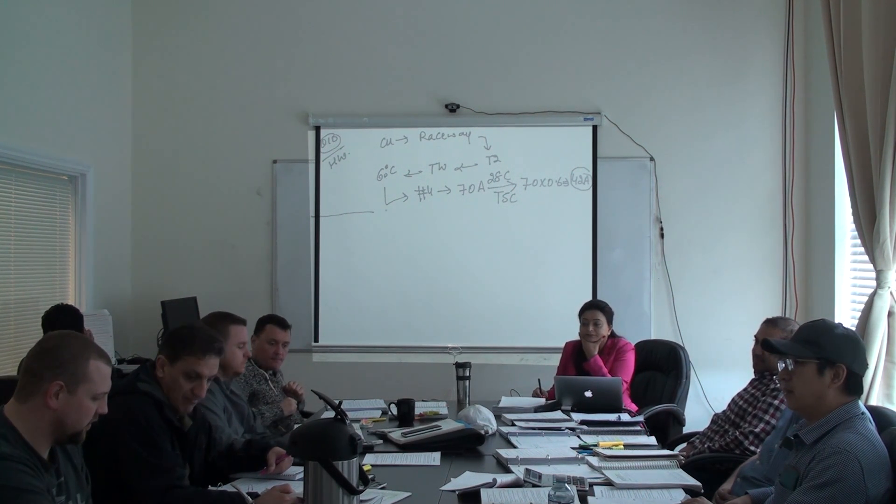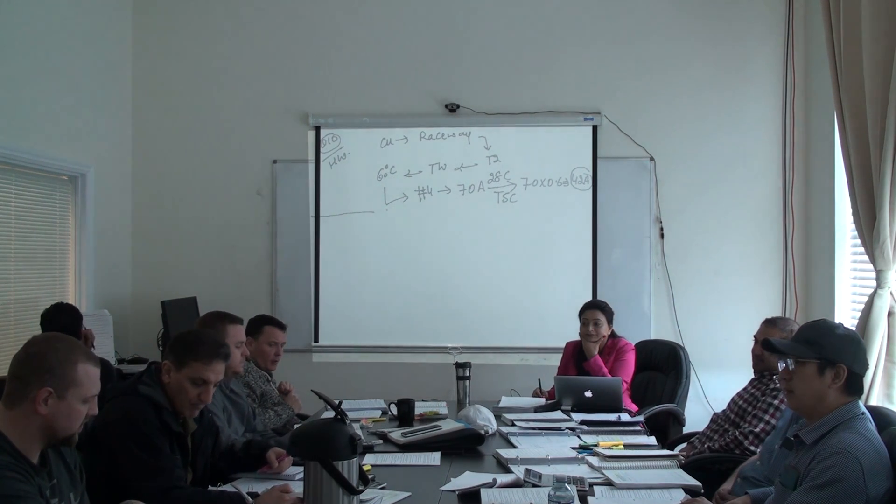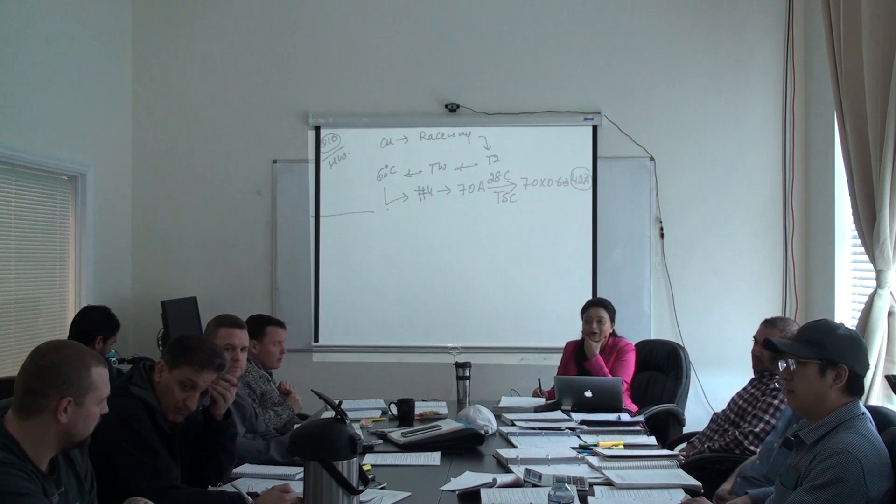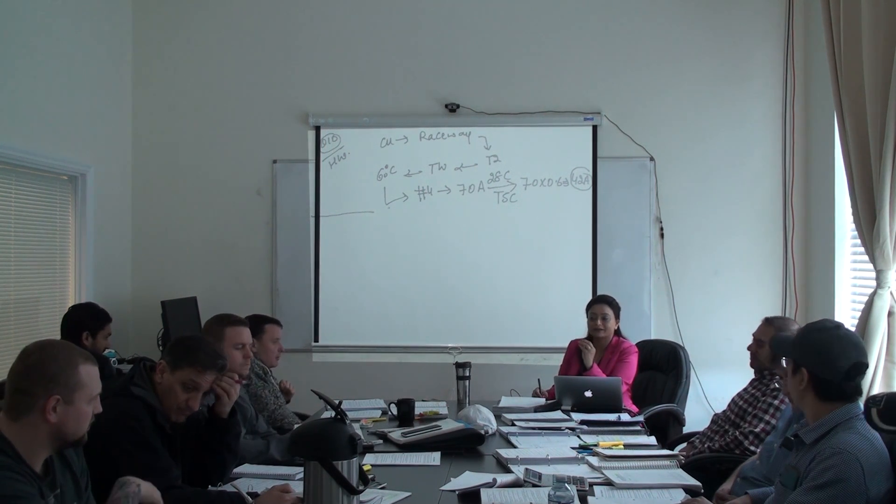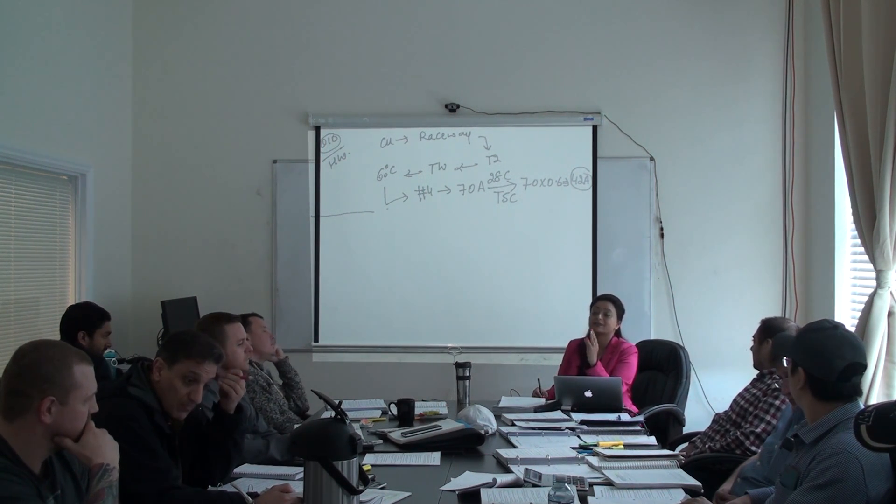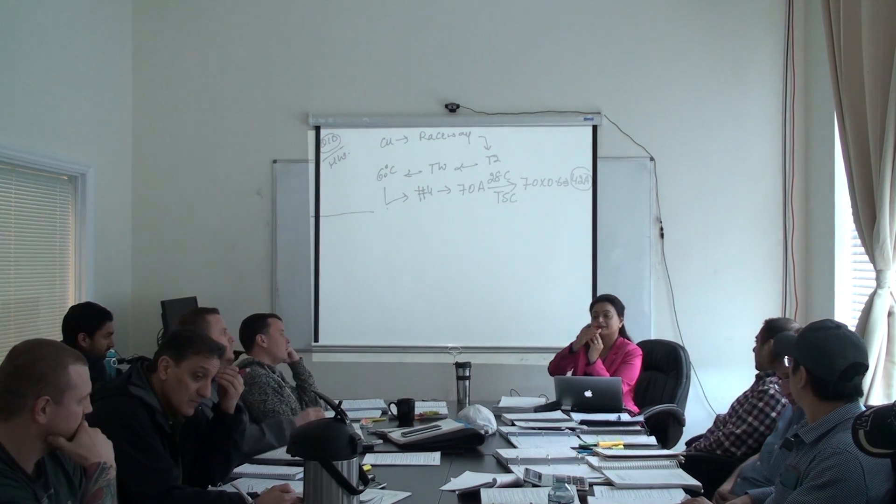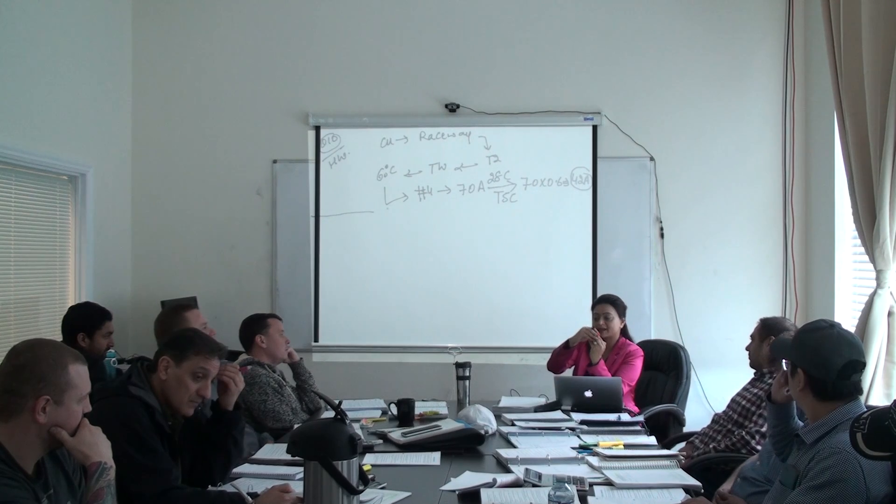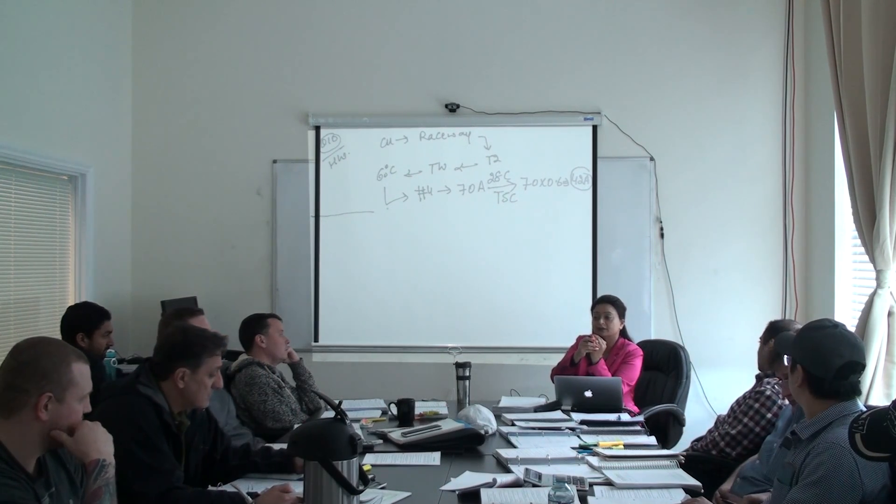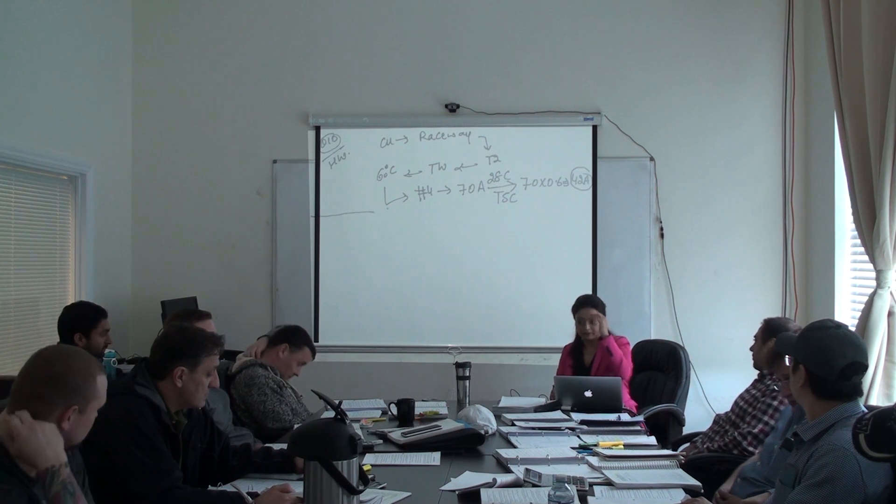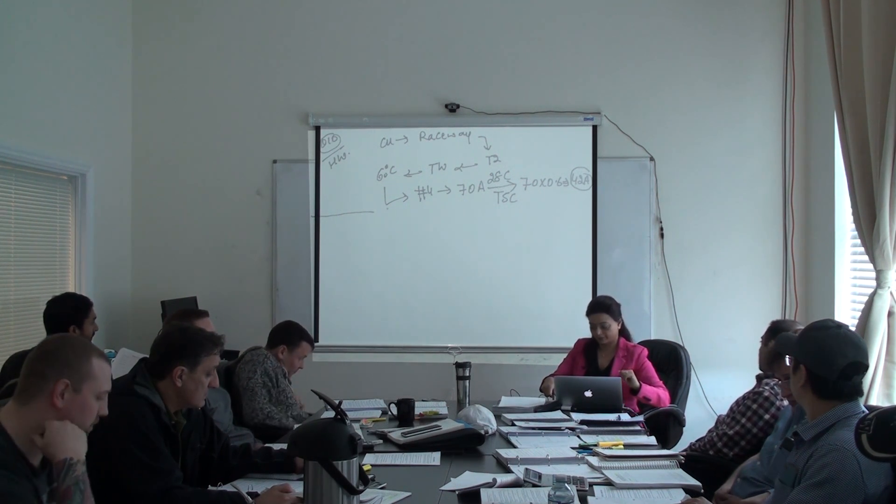In previous code books, was there language of current carrying conductors? We're going to talk about that. When there is a three phase four wire system, you have three phases plus a neutral and it's a balanced system, so each wire is carrying 100 amps. What's the current in the neutral? Zero. In that case you don't count it. We're going to talk about this when we highlight more stuff in section four.